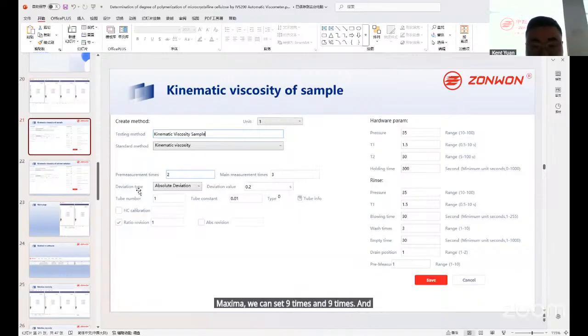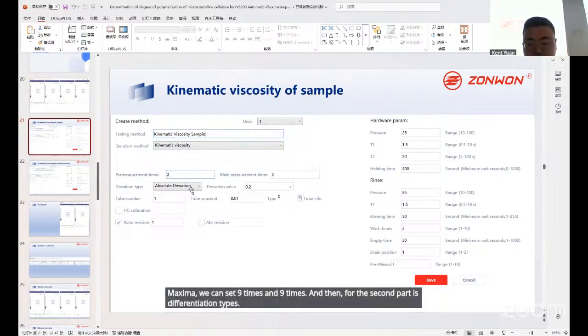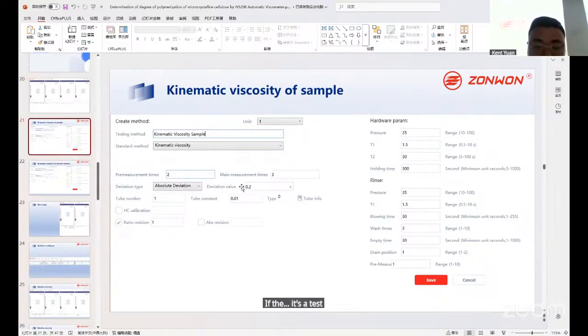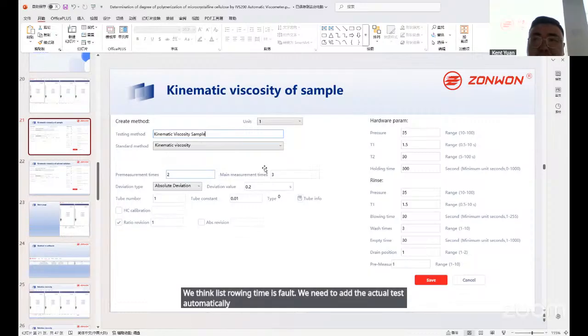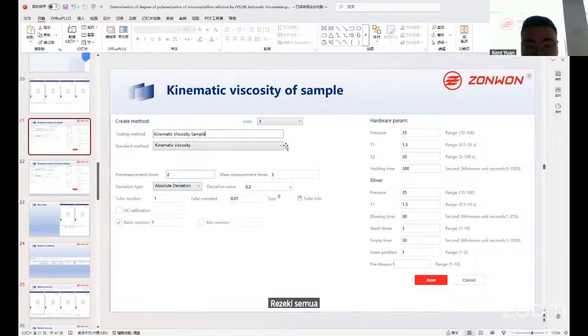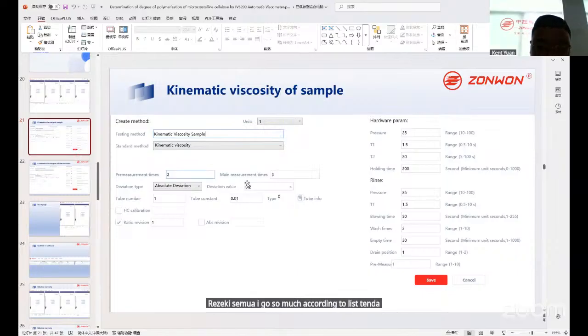For the second part, differentiation types: if it's tested 3 times but one of the times the deviation is higher than 0.5 seconds, we think this flowing time is faulty. We need to add an extra test automatically to make the result more accurate. So we set the deviation time at 0.2 seconds according to the standard. That means if one of the tests is beyond the deviation, the machine will do extra testing automatically to make sure the result is more accurate.